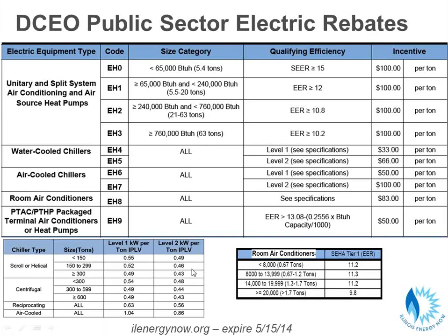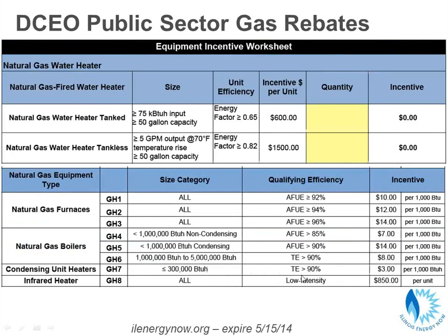Once again, click on this. There are gas rebates from the utility. These are currently higher than normal because the gas program is fairly new, so they're trying to get awareness out about it. So they've increased the rebates up substantially. So furnaces are, based on the size of the furnace, anywhere from $10 to $14 for every 1,000 BTUs. So if you put in a 100,000 BTU furnace and it was 95% efficient, you would get a $1,200 rebate in your commercial building. Boilers, similar.